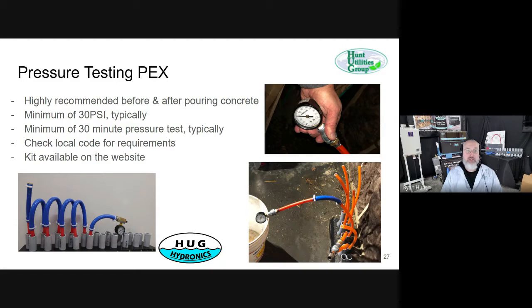So we sell these kits. Since we don't have a typical pressure testing kit for PEX, they'll have a manifold that they all connect to at one point. Since our system doesn't require the manifold, we sell this kit to be able to daisy chain them together. You can put as many loops as you want all together like that. And then we've got the end. You add air, minimum 30 PSI. Some codes will require much higher and for longer time. And a lot of people will leave that pressure gauge on there as they are pouring the concrete, just to make sure that nothing gets damaged.